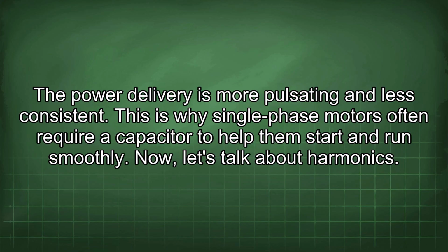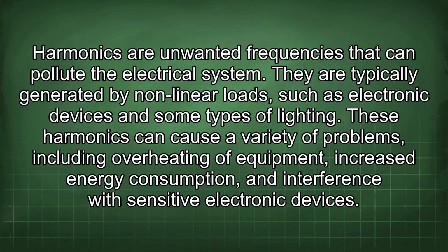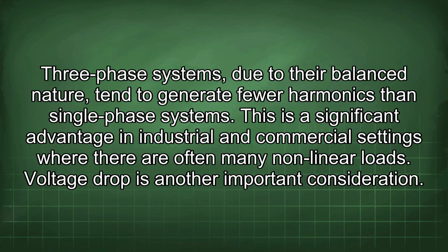Now let's talk about harmonics. Harmonics are unwanted frequencies that can pollute the electrical system. They are typically generated by nonlinear loads, such as electronic devices and some types of lighting. These harmonics can cause a variety of problems, including overheating of equipment, increased energy consumption, and interference with sensitive electronic devices. Three-phase systems, due to their balanced nature, tend to generate fewer harmonics than single-phase systems. This is a significant advantage in industrial and commercial settings where there are often many non-linear loads.